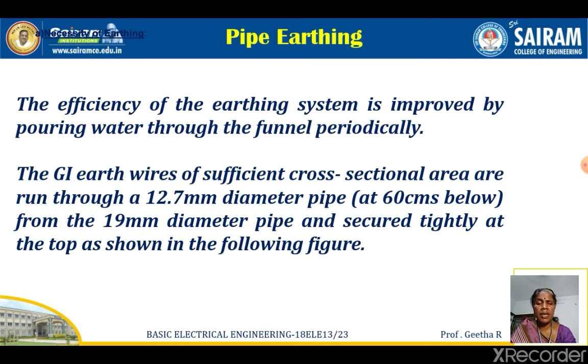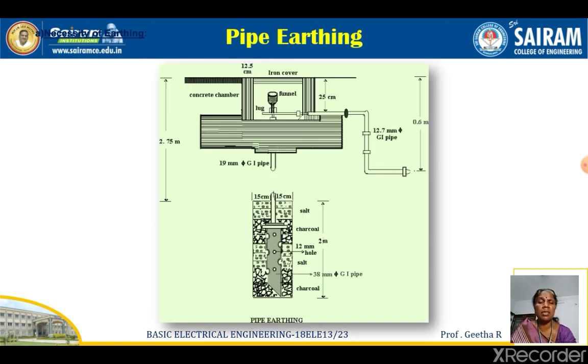The GI earth wires of sufficient cross sectional area are run through the 12.7 millimeter diameter pipe at 60 centimeters below the 19 millimeter diameter pipe and secured tightly at the top, as shown in the figure. You see here the tube used, through which the electrical wiring is fixed. This chamber is filled with coal and salt alternately. Here the continuous wiring will be. Here it is the chamber. You can see the funnel here. Through that funnel, water can be poured to maintain the electrode at low resistance.